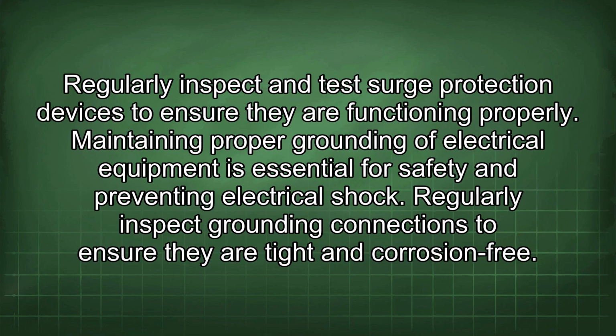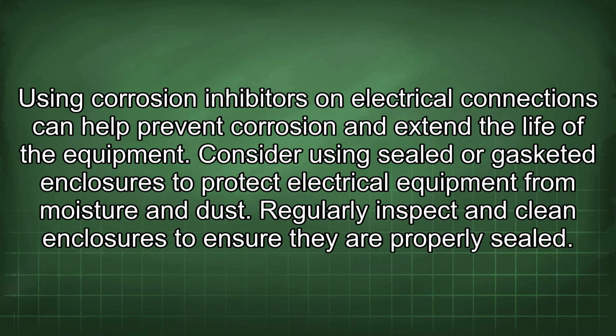Regularly inspect and test surge protection devices to ensure they are functioning properly. Maintaining proper grounding of electrical equipment is essential for safety and preventing electrical shock. Regularly inspect grounding connections to ensure they are tight and corrosion-free. Using corrosion inhibitors on electrical connections can help prevent corrosion and extend the life of the equipment.